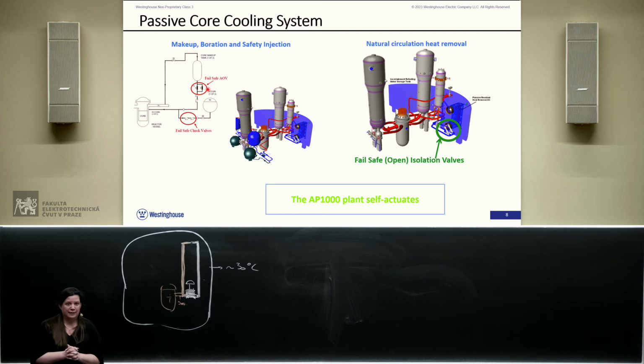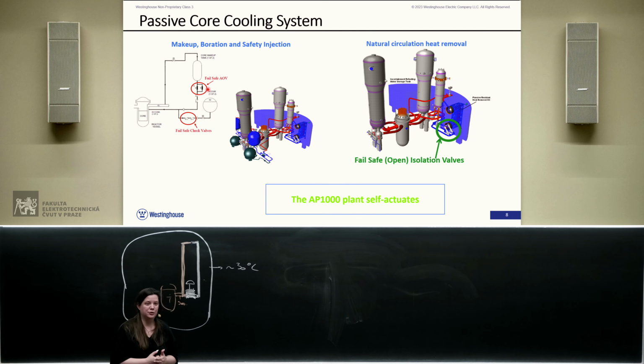Jing mentioned we don't like needing power at all. An instrumentation and control system still requires power to function. Compared to a system that would do the same function by using a pump to inject into a 155 bar pressurized system, we're using much less electricity than that solution. But we still use a bit. We use a bit to have our control system monitoring the core and to open the valve.